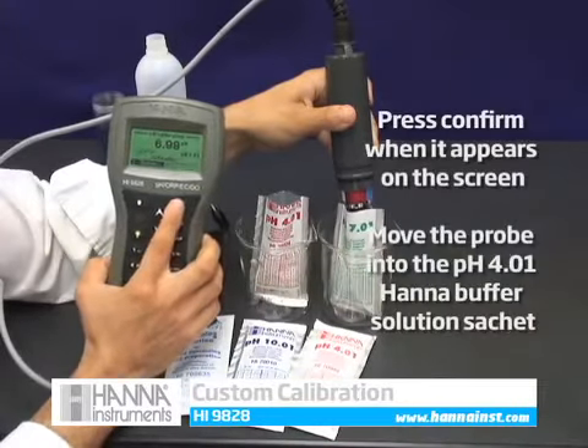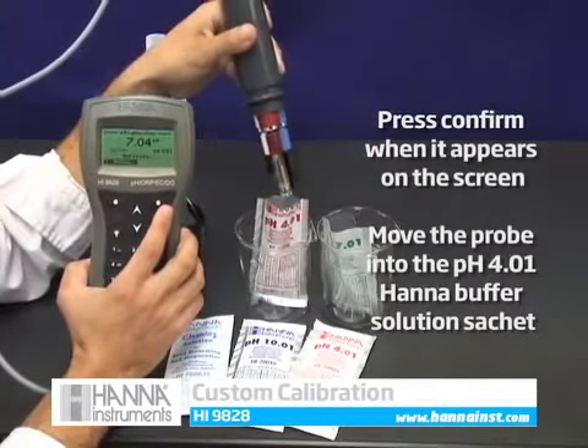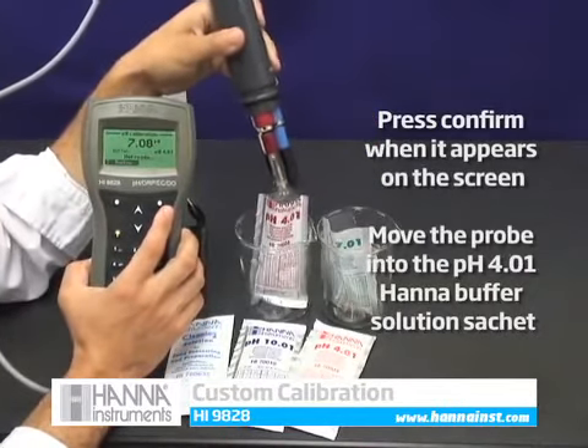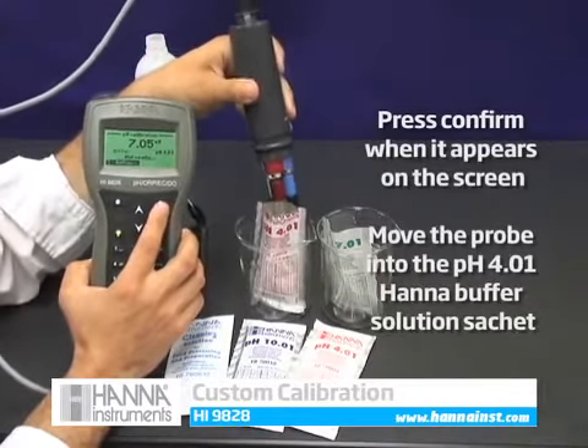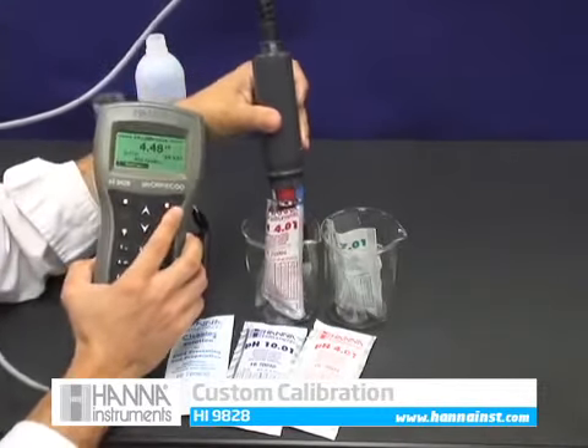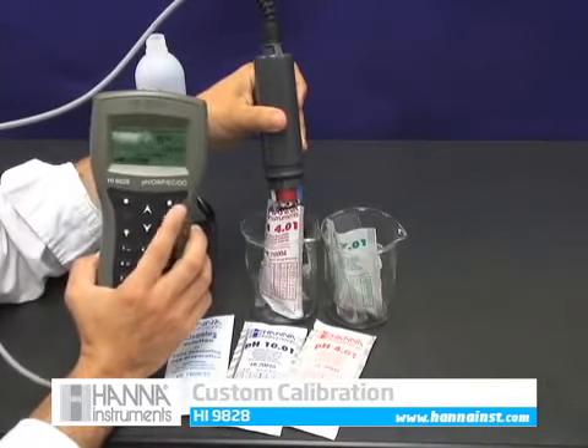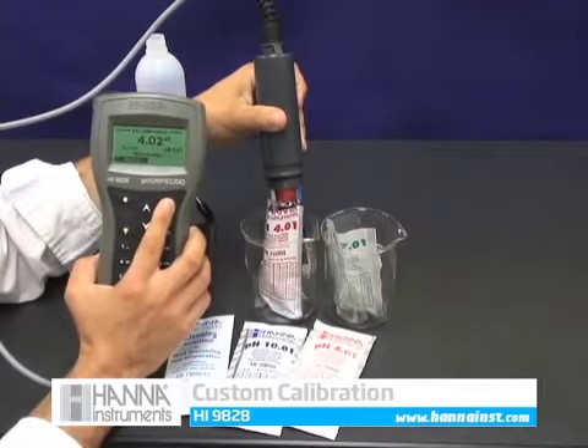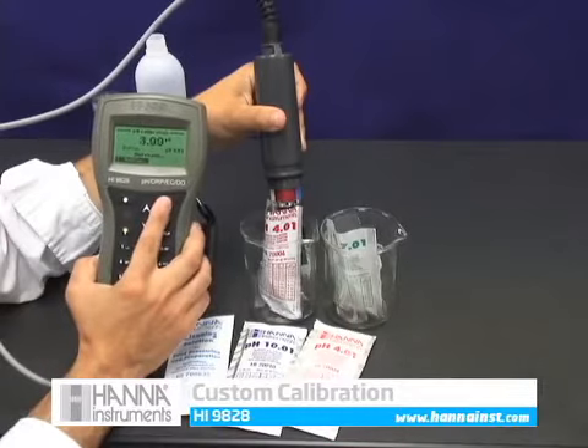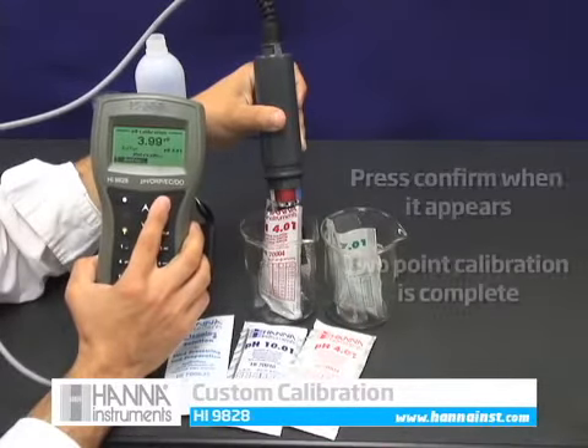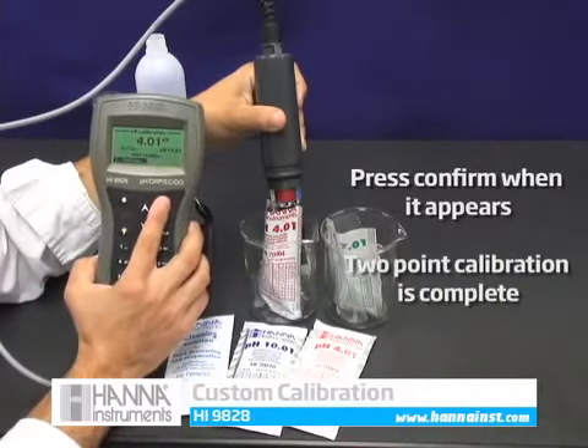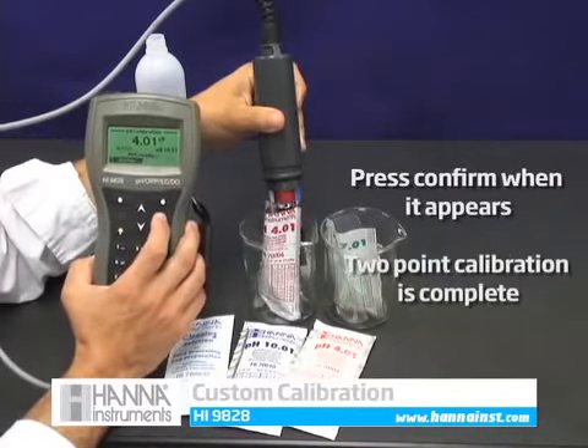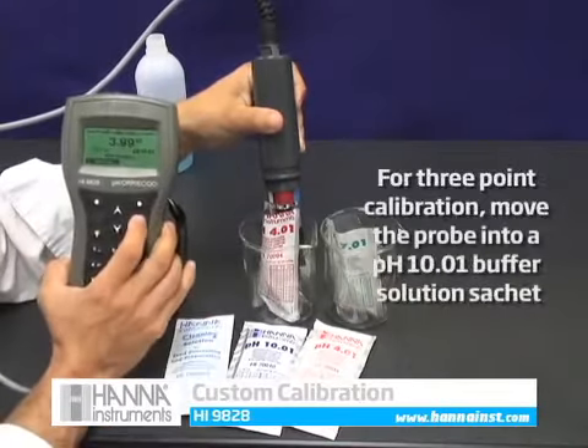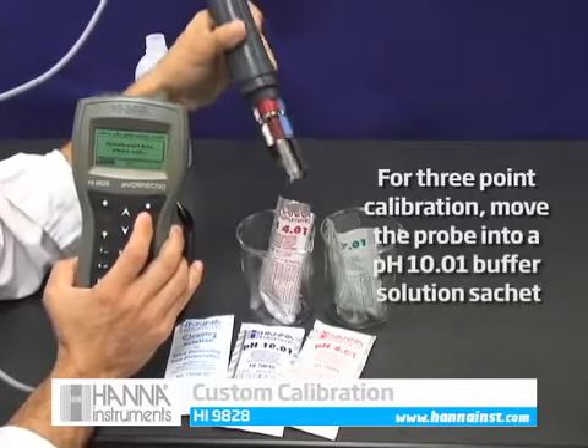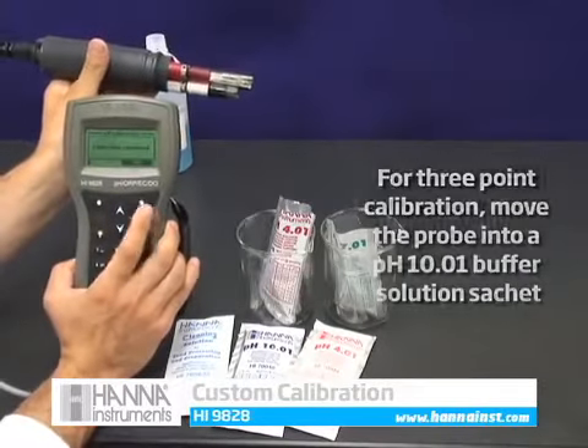When the reading stabilizes, Confirm will appear on the screen. Press Confirm and move the probe into the pH 4.01 buffer solution sachet to begin calibrating the second point. Again, press Confirm when it appears on the screen. Your 2-point calibration is complete and you may begin using your meter. For a 3-point calibration, simply move the probe into a 10.01 pH buffer sachet after confirming the pH 4.01 calibration.